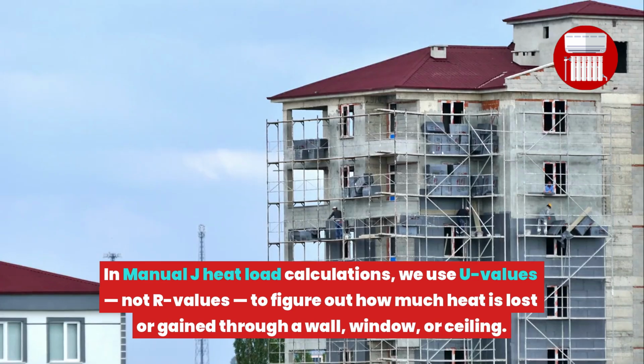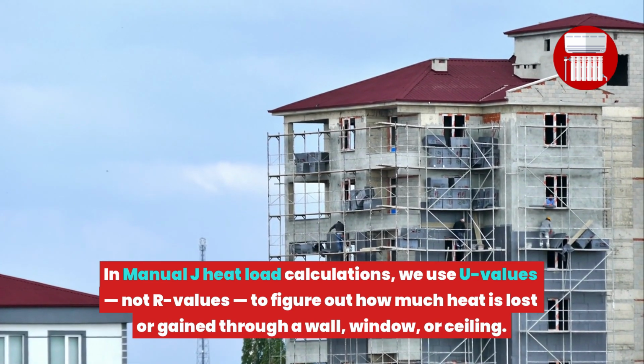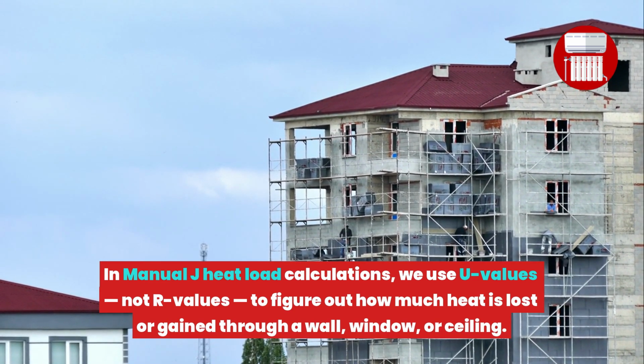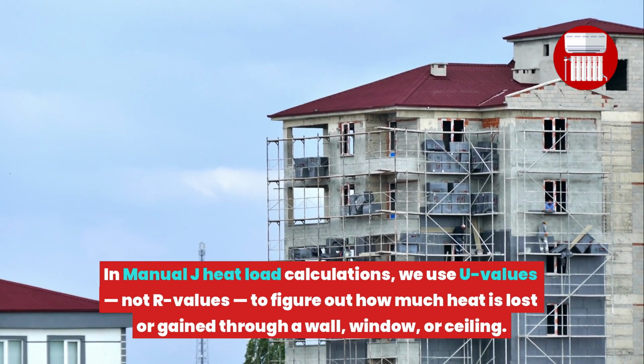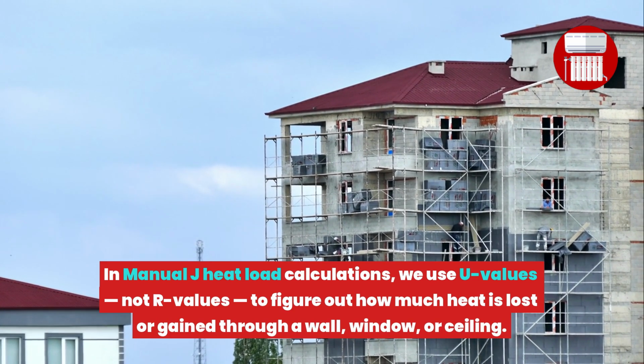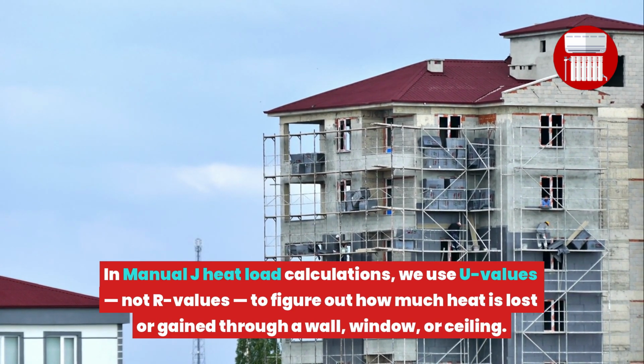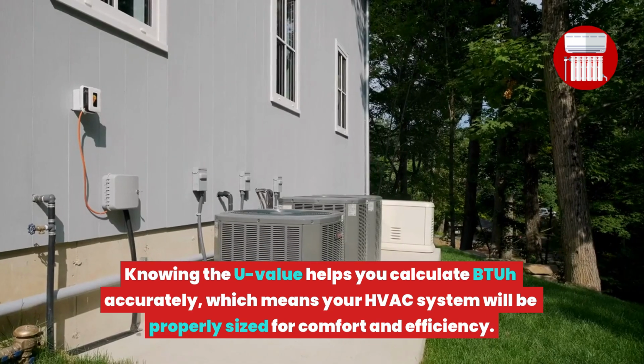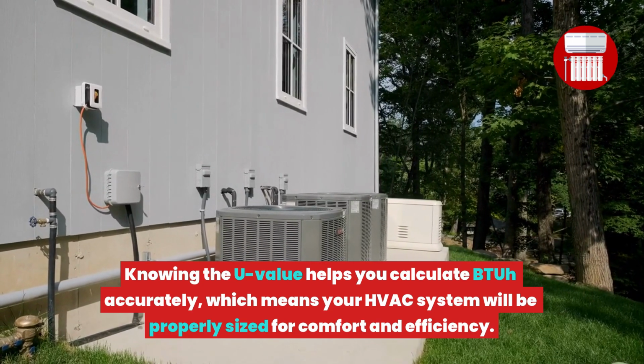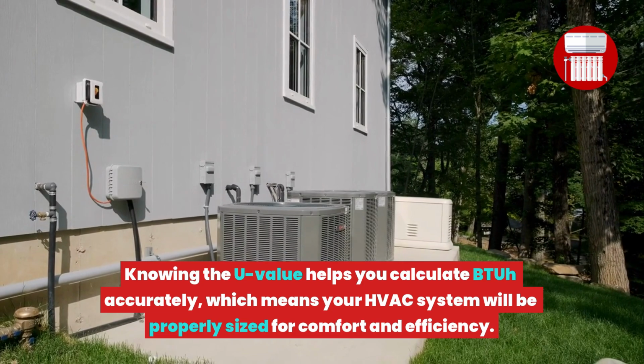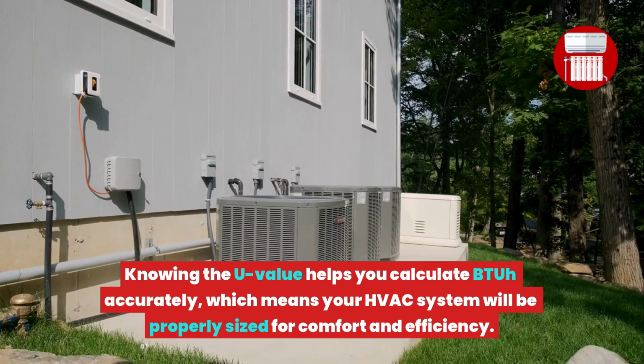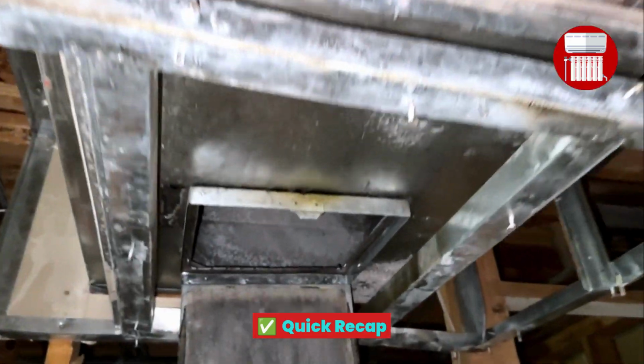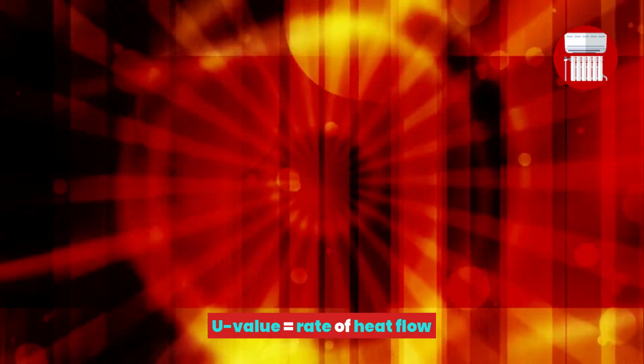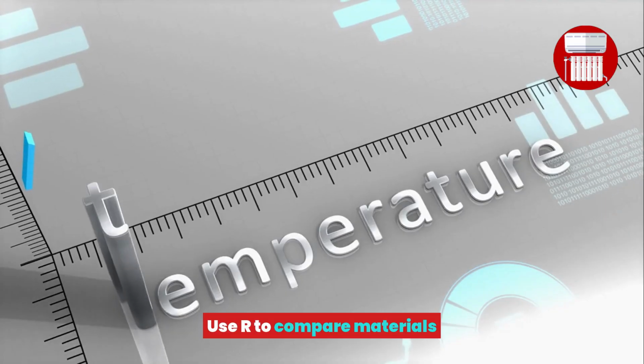Why it matters in Manual J heat load calculations, we use U values, not R values, to figure out how much heat is lost or gained through a wall, window, or ceiling. Knowing the U value helps you calculate BTU accurately, which means your HVAC system will be properly sized for comfort and efficiency. Quick recap: R value equals resistance to heat, U value equals rate of heat flow. Use R to compare materials, use U to calculate heat load.